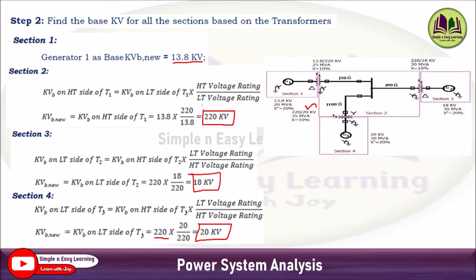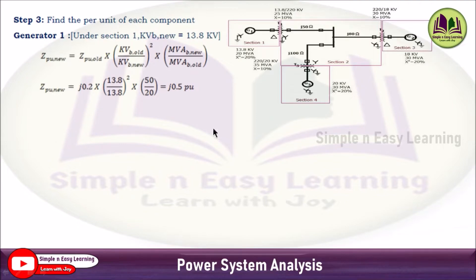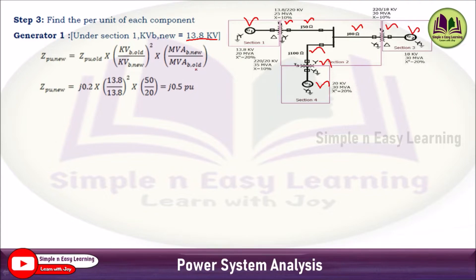Now find the per unit impedance of each component: generator G1, transformer T1, transmission lines 1, 2, and 3, transformer T2, generator G2, transformer T3, and generator G3. Starting with generator G1 in section 1 (base kV = 13.8 kV), apply the formula: Z_pu_new = Z_pu_old × (KVB_old/KVB_new)² × (MVAB_new/MVAB_old) = j0.2 × (13.8/13.8)² × (50/20) = j0.5 per unit.